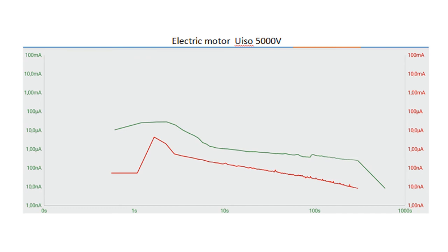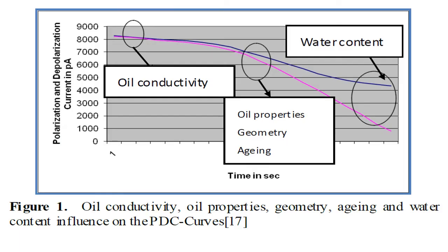So generally those were some examples of the PDC curves. Now to determine what's the condition of this object, the best will be to in some time do again the PDC test and compare the graphs. So as I already mentioned, the most important advantage of this type of method is that it gives you full picture of what's happening in the isolation even before any failure will appear. So still the value of the resistance could be okay but using this method you can determine if in the short or longer future there will be any problem with this isolation.